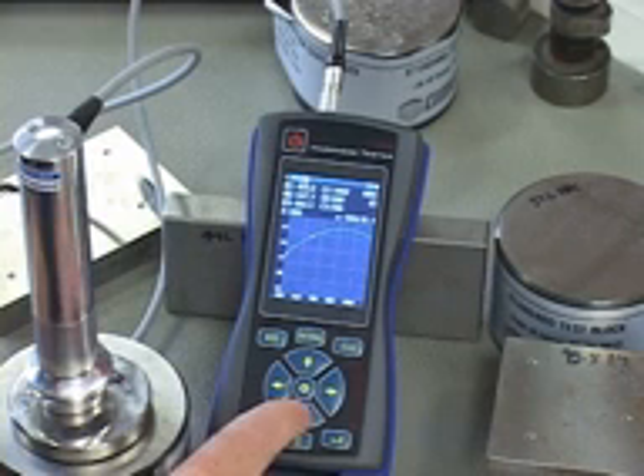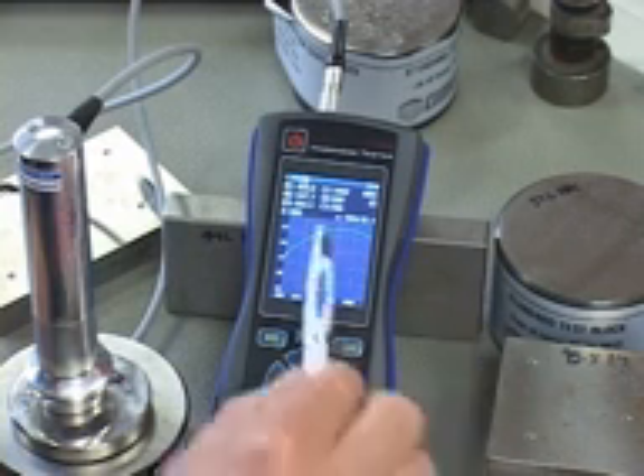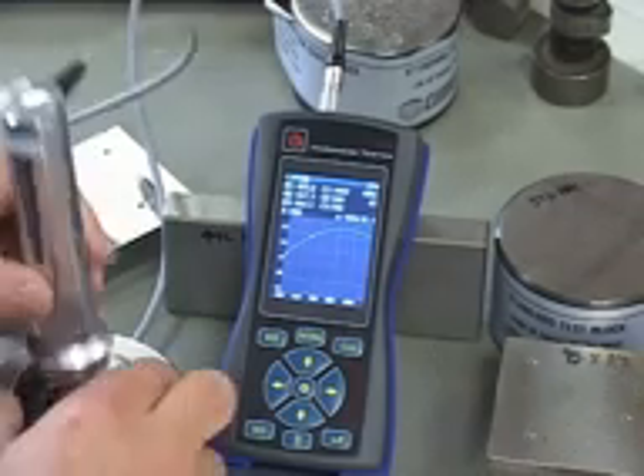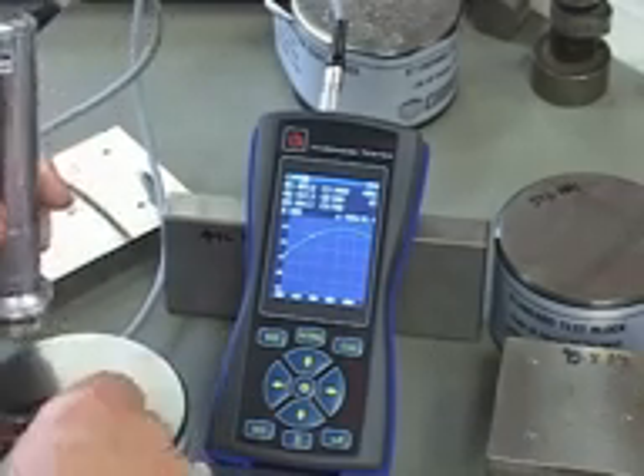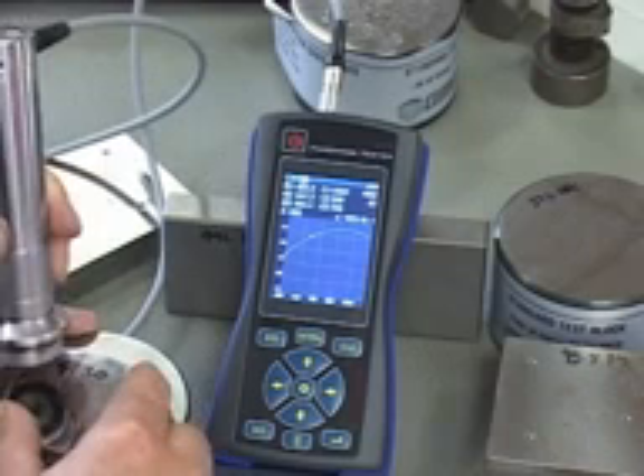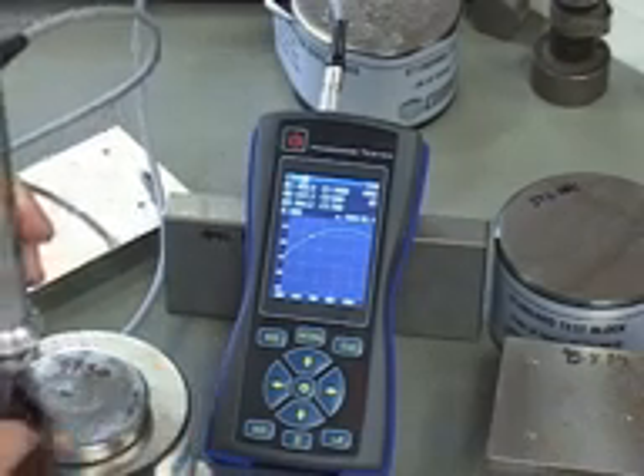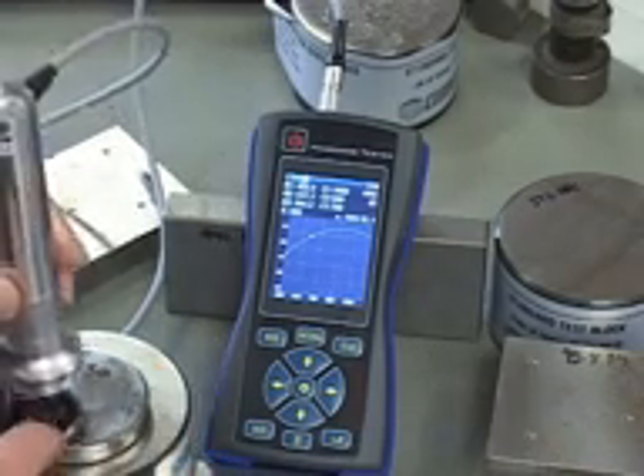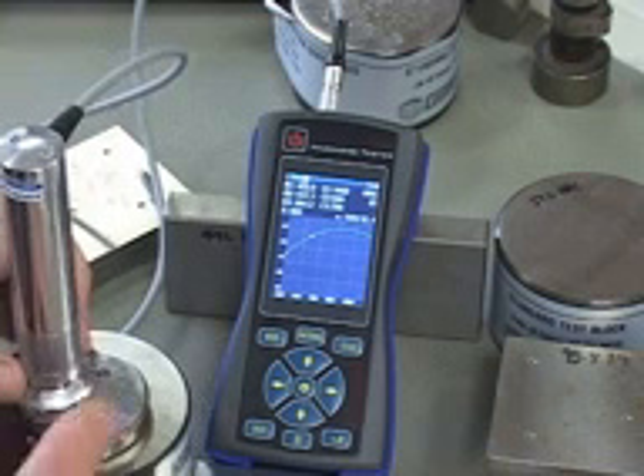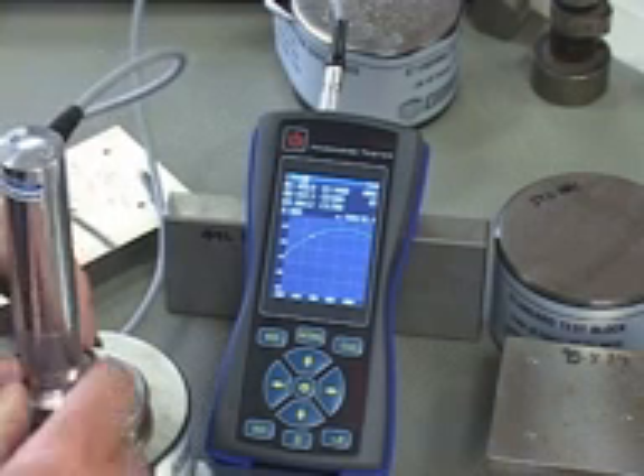So I'm just going to go down to the next one. And so now I've highlighted the second line in yellow, and I'm going to put on my 47.3 calibration block. I ring it to the part, so now it's almost stuck to it, and it's thinking that the part is heavier and denser, but we're actually just testing the material on the top, not all the way through.